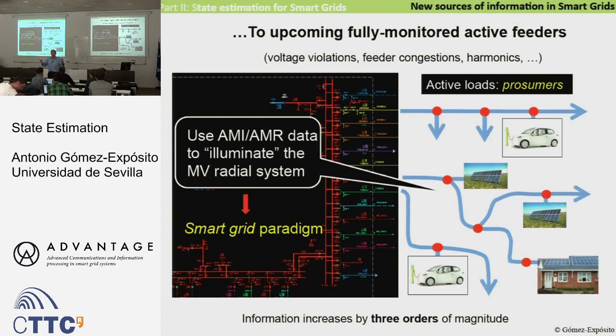They are not more or less accurate than conventional measurement. It depends on the instrumentation transformers. If they use the same instrumentation transformers as conventional measurement devices, they have the same accuracy. So sometimes people claim PMUs are so accurate that we can get rid of state estimation. This is false. It's not true.